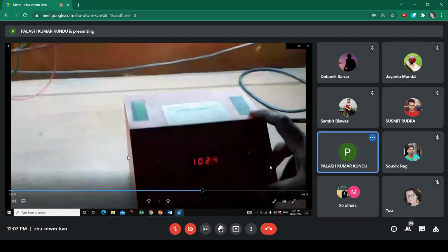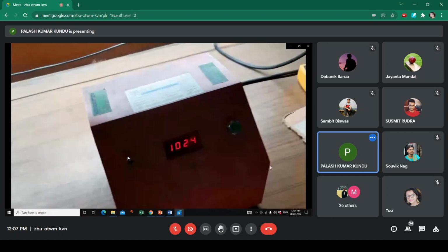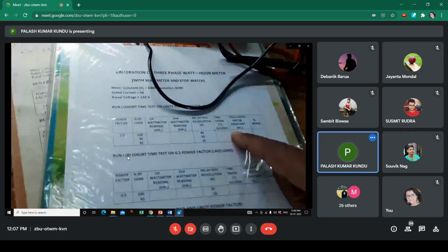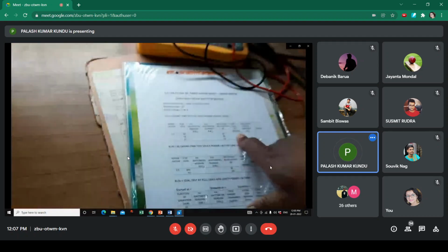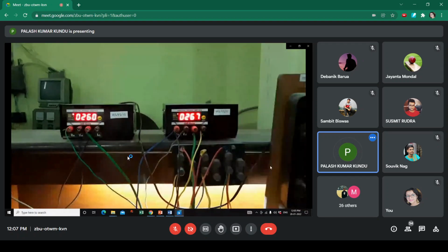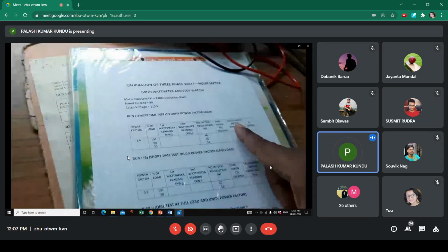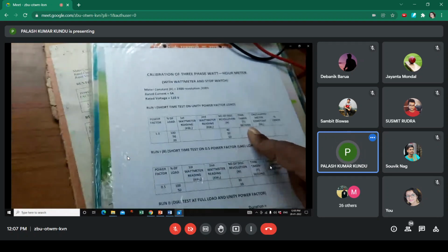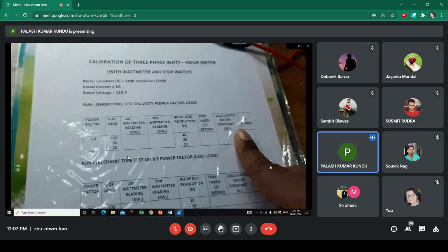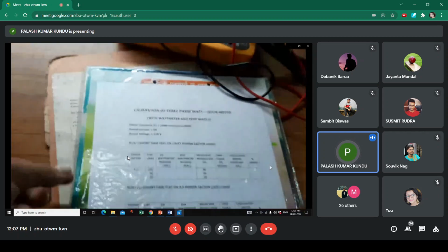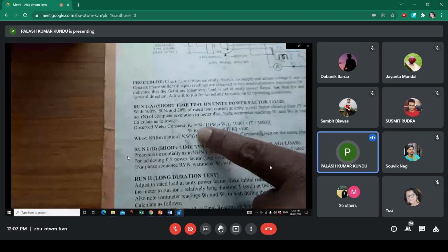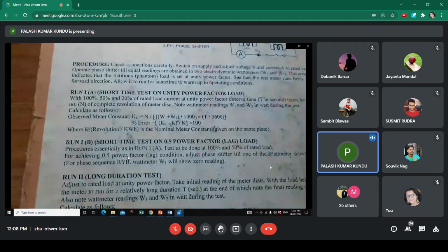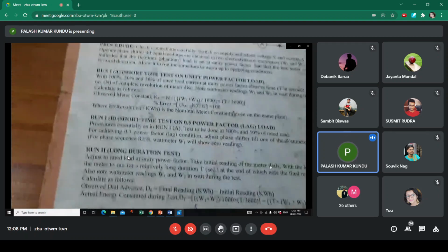In 40 revolutions, I got the time of 102.4 seconds. You have to note it down here: the time taken in seconds, and also the wattmeter readings W1 and W2. The number of disc revolutions, 40, we know already, and the time taken is 102.4. Then the calculated meter constant, Kc. All the formulas are given in your worksheet. You have to calculate the value of Kc using W1, W2, and T.